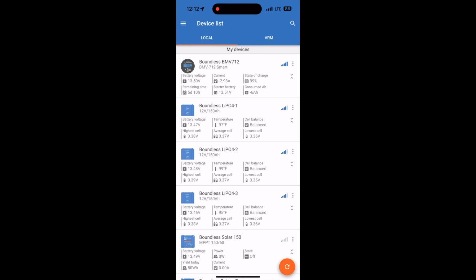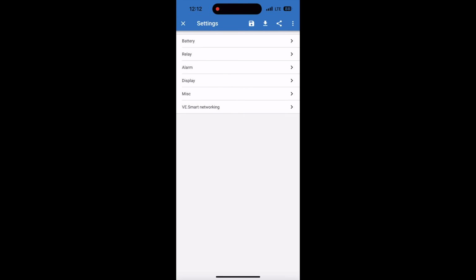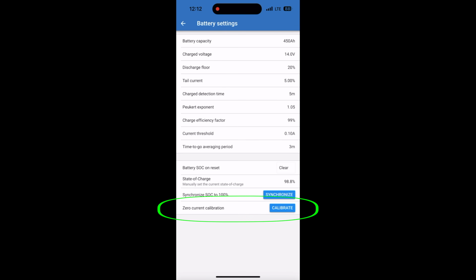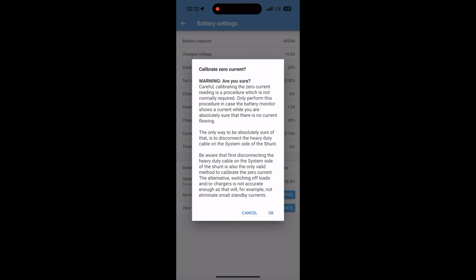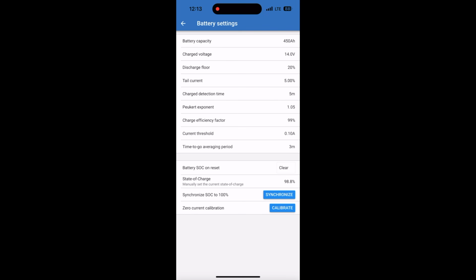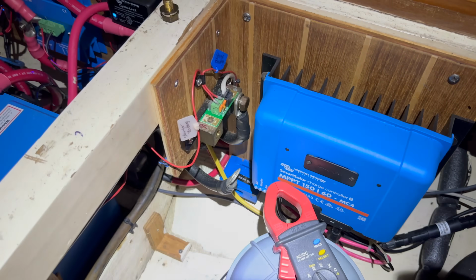All right, so here we are in the Victron app, and we can see everything transmitting Bluetooth data on our boat. I'm going to connect to the BMV, which is the battery monitor. Here in the settings we'll find the zero current calibration. And here's where it gets interesting: the app warns that a zero current calibration will only be accurate if there is truly zero current flowing. The only way to be sure of that is to disconnect the system negative from the shunt, shutting down the entire system. So here I backed out of the calibration and disconnected the system negative.